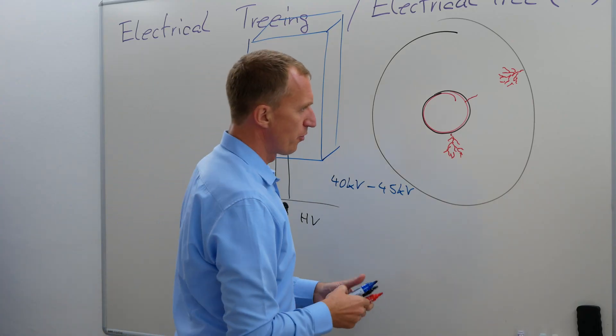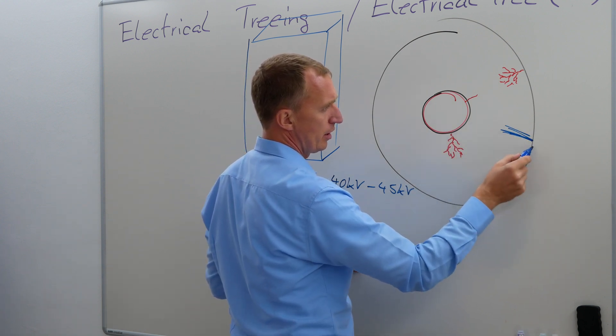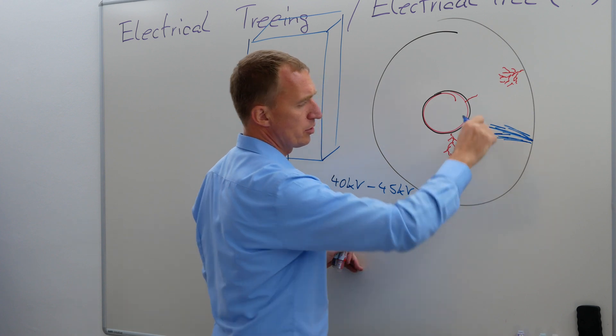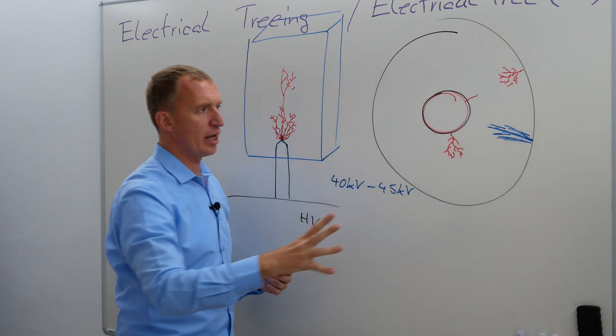What happens is, if you have water ingress, it can come from the inside or from the outside, and you have like a water tree going here. Usually it doesn't have so many branches. What happens is, the electrical field will change.